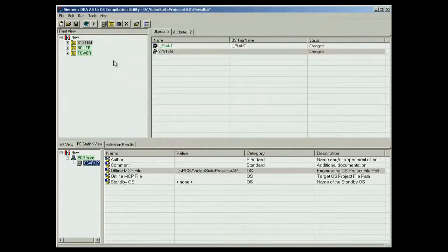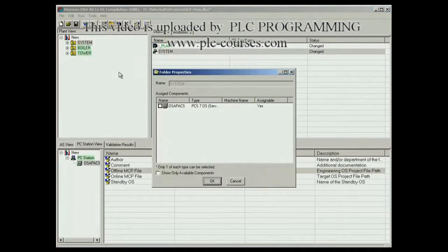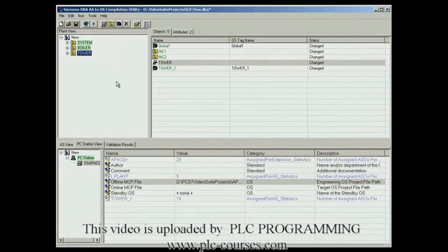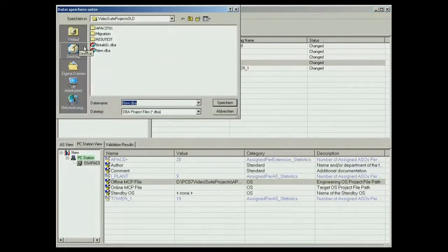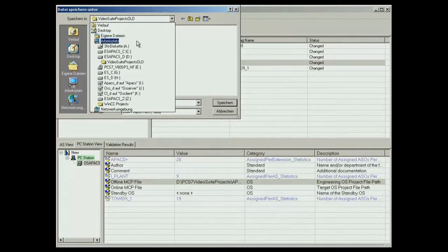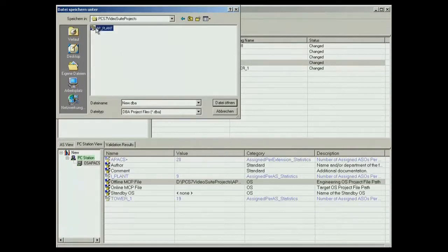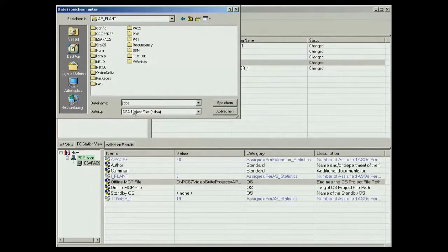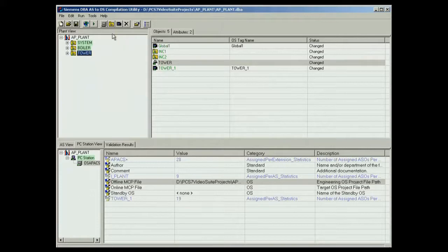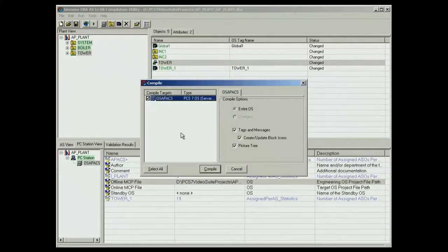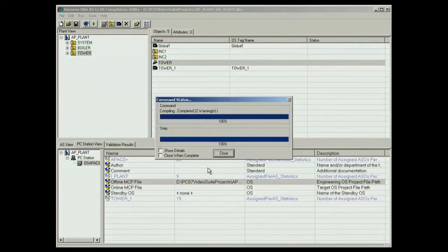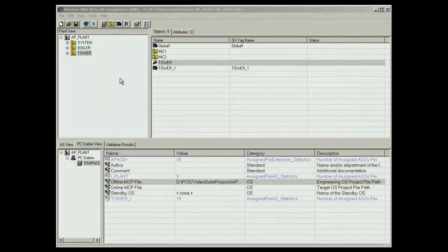The picture hierarchy objects must now be assigned to the OS. This is necessary because a DBA project can include several operator stations. The DBA project is saved in the path of the OS and the OS is compiled. The first time the project is compiled, it is compiled completely. The tags, messages, block icons, and the picture tree are created. This completes all the work in DBA.